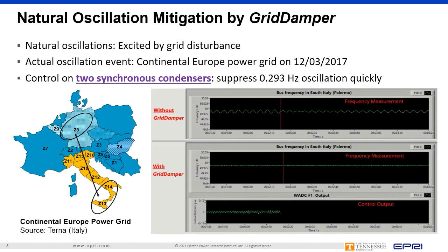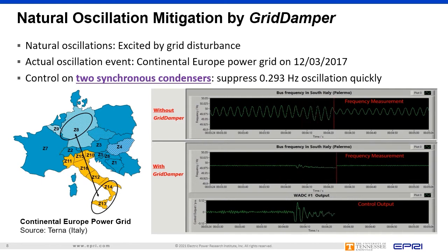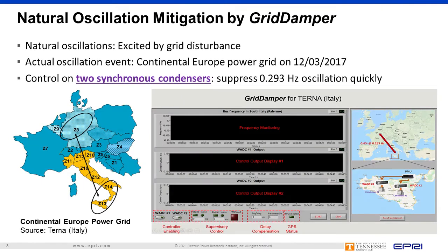The video on the right compares oscillation dynamics with and without Grid Damper. Without Grid Damper, the oscillation kept growing. By contrast, when Grid Damper is in service, the oscillation settled quickly in three seconds with a magnitude close to zero.